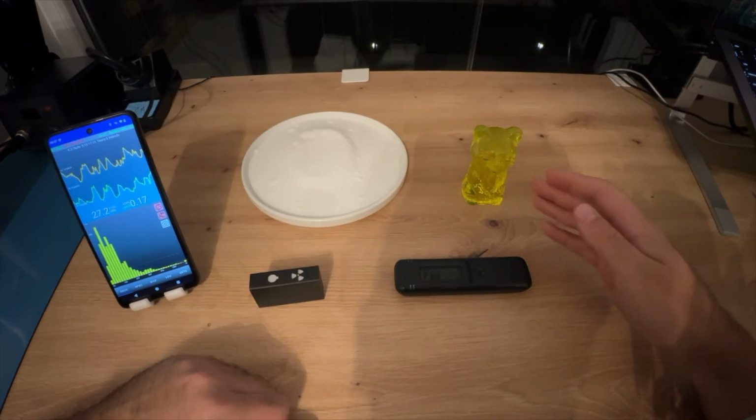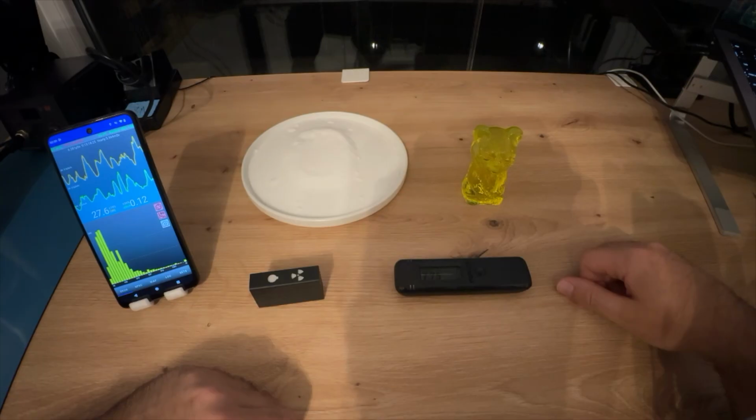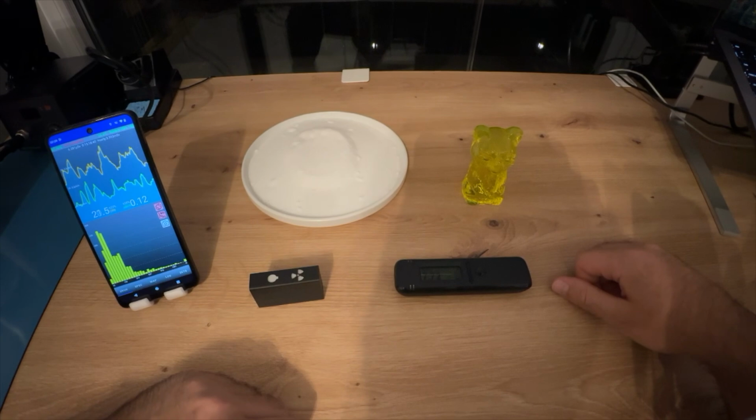As with uranium, it's a totally different story. Uranium decay schemes are long and different for different isotopes. Even the decay of a single uranium isotope, U-238, the most common one, consists of over 15 steps. And there are three naturally occurring isotopes of this element. It makes the spectrum analysis complicated, and practically only professionals are able to do spectral analysis. It is also quite a good benchmark for our testing of the products, to see if they are able to provide good enough resolution to understand what we are measuring.